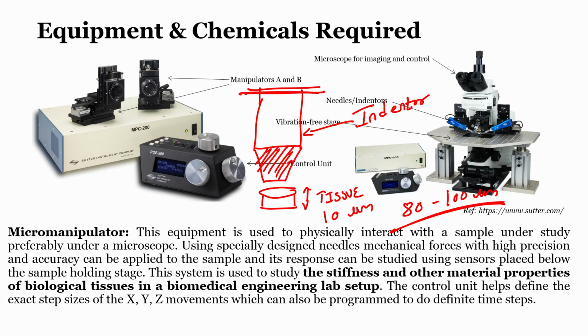So if I want to understand the stiffness of the tissue, how stiff my tissue is, what will I do? I will indent the tissue, I will press the tissue, and I have to indent it by going down a few microns in the z direction, right. So I have to use an indenter, but how can I control a few microns of pressing the tissue? A few microns is possible with the help of a manipulator, and that manipulator is my XYZ manipulator, also called a micro-manipulator, and that is why it is called micro-manipulator. Okay. It can control the movement of my indenter in Z, in X or in Y, with a precision of a few nanometers actually, but a step size of a few microns. It is really accurate.